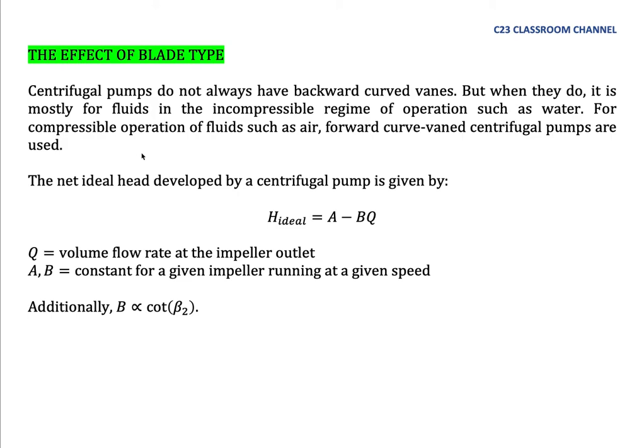The net ideal head developed by a centrifugal pump is given by H_ideal equals A minus BQ, where A and B are constants for a given impeller running at a given speed, and Q is the volume flow rate at the impeller outlet. Sometimes when you buy a pump, the manufacturer will give you this equation—the values of A and B—to represent the ideal pump head for that centrifugal pump.